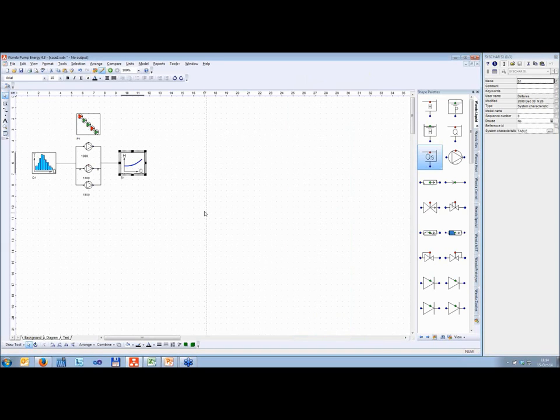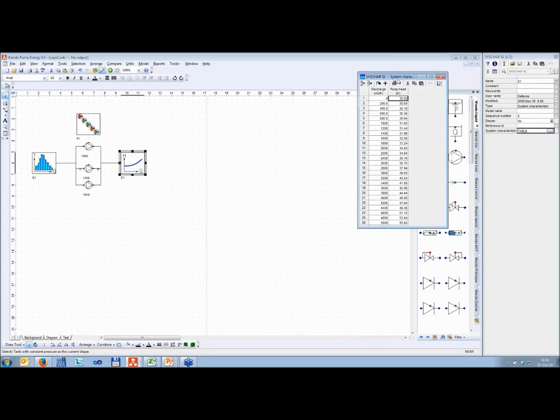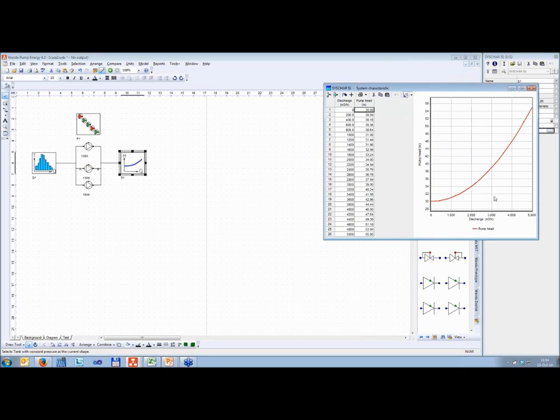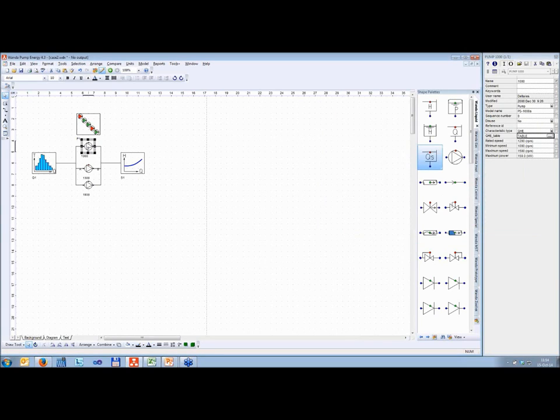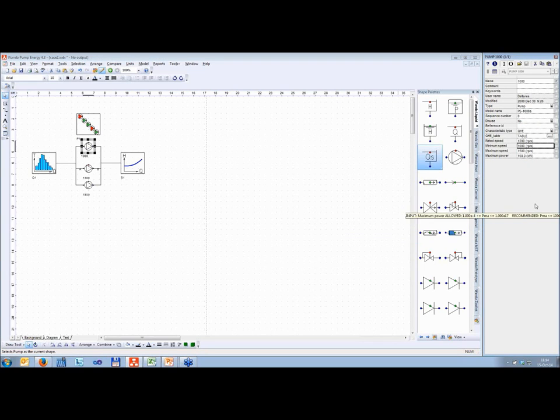The second thing you have to put in is the system characteristic. You can see it's a nice parabolic curve with a static head of 30 meters. You can calculate this yourself, or as I said, you can use the system characteristic module to determine it and just copy it in. Next, of course, you have to put in the pumps with some additional data: the minimum speed, the maximum speed, and the maximum power it can use.